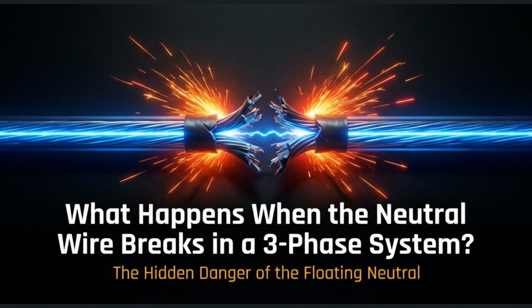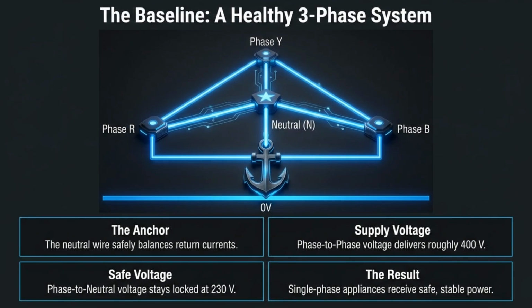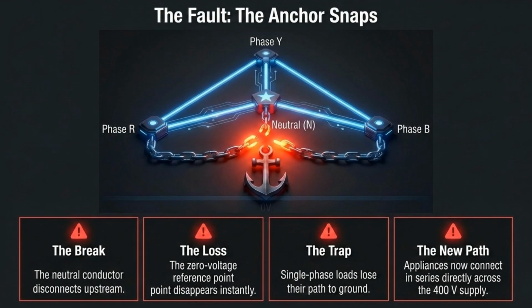In this video, we explore the serious risks associated with a broken neutral wire in a three-phase electrical system, often referred to as the hidden danger of the floating neutral. In a healthy three-phase system, the neutral wire acts as an anchor, balancing return currents and keeping the voltage supplied to your appliances stable at 230 volts. When the neutral wire breaks, that essential anchor is lost. This disconnects the zero voltage reference, forcing your appliances into a new, dangerous electrical path.